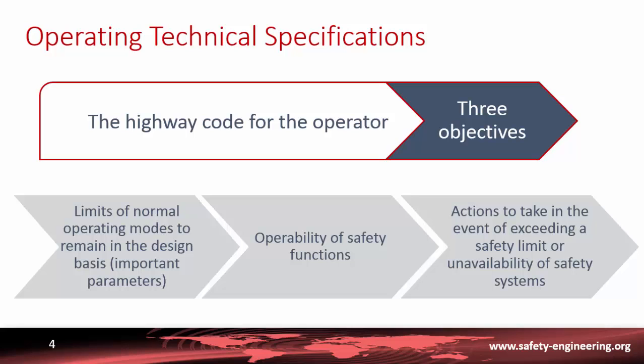For example, when calculating a loss of coolant accident, the increase in pressure and temperature of the containment uses an initial containment temperature of 50°C in the calculation. So it is important during normal operation to ensure that the temperature inside the containment remains under 50°C, and this is included in the Operating Technical Specifications.